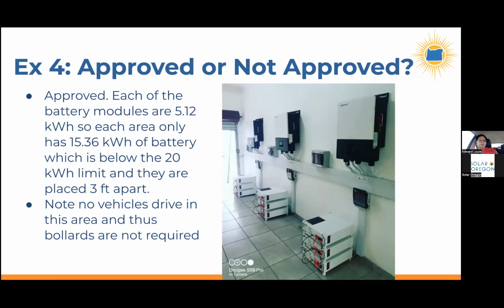All right, so what about this setup? Well, this setup would be approved because in this case, each of these batteries is 5.12 kilowatt hours. So 3 put together is still below the 20 kilowatt hour limit. And as you can see, they've placed each of the units 3 feet apart from each other. And so therefore, this would be allowed under the NFPA 855 rules. If this was in a vehicle driving area, then it would need bollards. But in this particular deployment, there are no vehicles driving in this area, so bollards are not required.